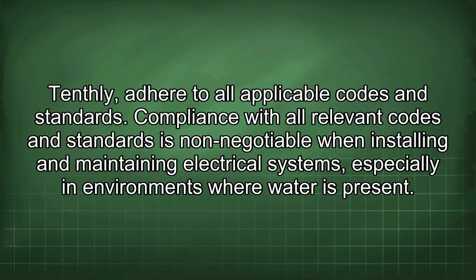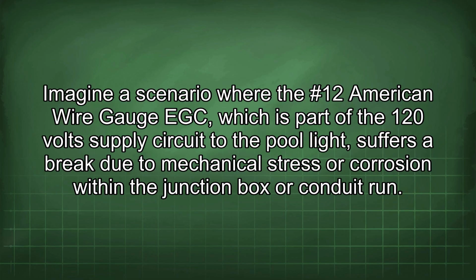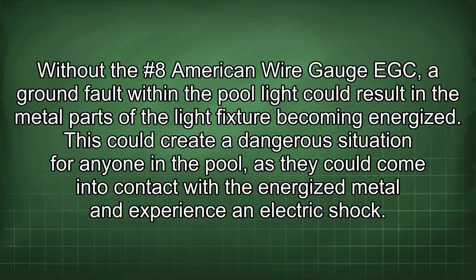Compliance with all relevant codes and standards is non-negotiable when installing and maintaining electrical systems, especially in environments where water is present. Imagine a scenario where the #12 American wire gauge EGC, which is part of the 120-volt supply circuit to the pool light, suffers a break due to mechanical stress or corrosion within the junction box or conduit run. Without the #8 American wire gauge EGC, a ground fault within the pool light could result in the metal parts of the light fixture becoming energized. This could create a dangerous situation for anyone in the pool, as they could come into contact with the energized metal and experience an electric shock.